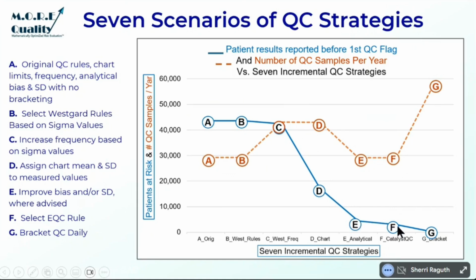And even with all that, Westgard will never recommend less than a 1-3s rule. And there are times that a 1-3s rule will simply not detect the size of shift you need to detect. So you can use better rules. So with all due respect to Dr. Westgard, he did it first, but we do it better.